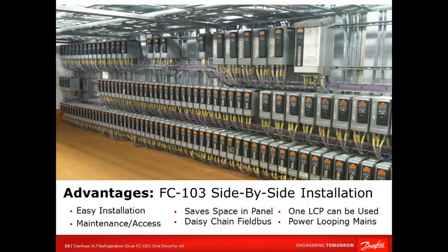One other thing we can do, this is just an example, and I like that it's actually from a brewery, is to show the capability where a lot of other manufacturers out there have to have space for cooling the electronics, where Danfoss capability is we just need certain space above and below, but we can go what they call book style. And the advantage is if you're putting our drives in a panel, for example, now you have less panel space required, or maybe fewer panels. So again, we're trying to make it easy and really to take up less space. If you're using field bus, let's say Ethernet IP, you can daisy chain. So basically you can make a true ring configuration daisy chain. Again, we're trying to make it faster for commissioning and setup, power loop the mains, easy to get access to the product. Again, just to be easy to work with.